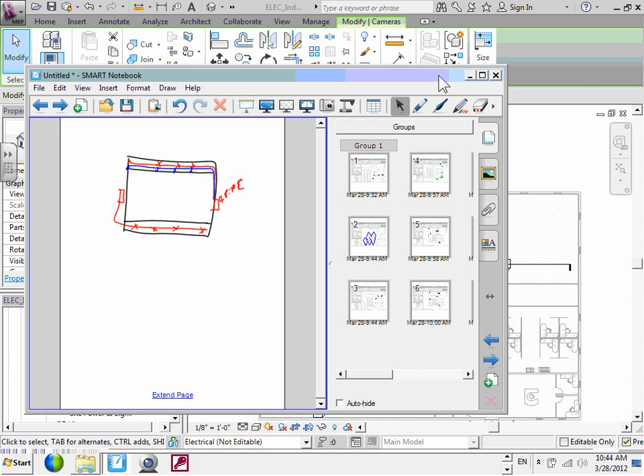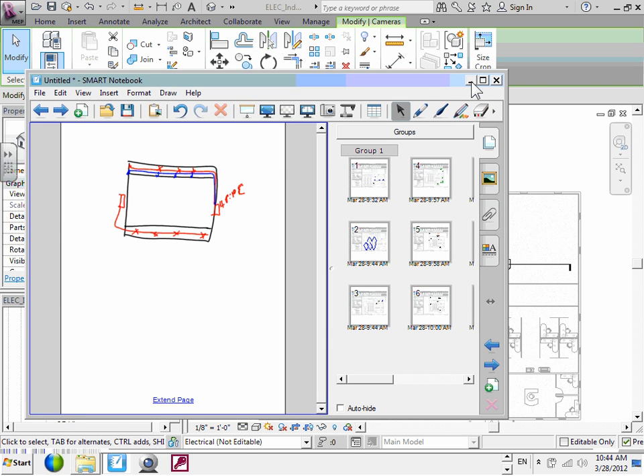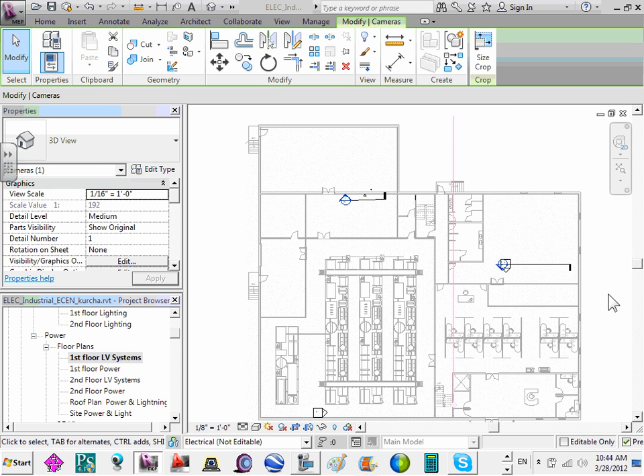As a standard, what our company has done is we do not use wire nuts. We have terminal strips. We put in a big junction box and we use the terminal strips and everything. All our wire is color coded to a certain standard that we have. Strobe is green stripe. Your data loop is going to be just red. Your speakers are going to be blue stripe. Power is yellow. And we let the building owner know so that when it comes to service, if they've got something going on, they can go to the panels where we have our terminal strips and do our testing right up here.